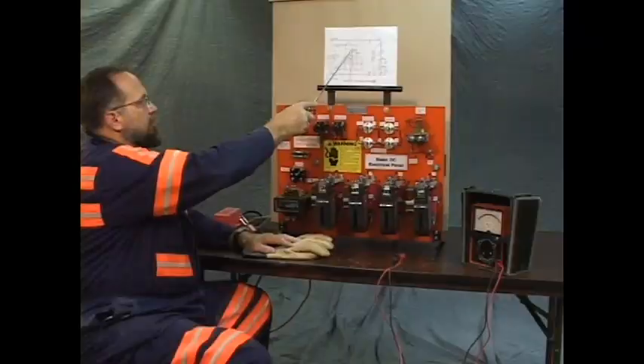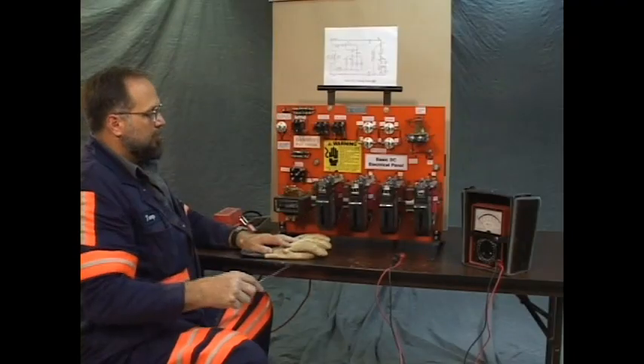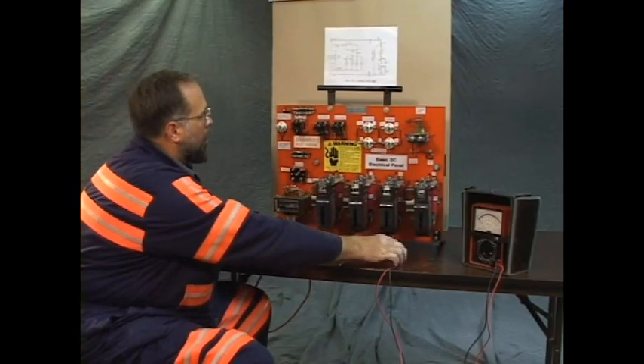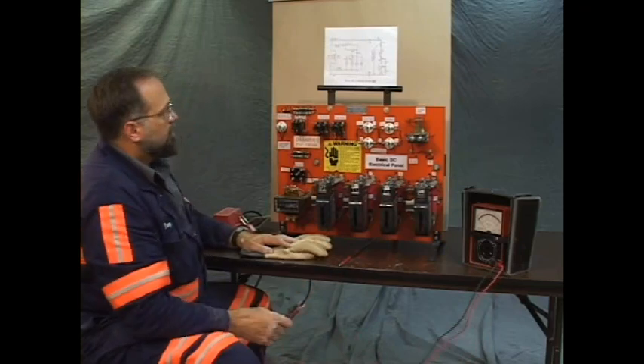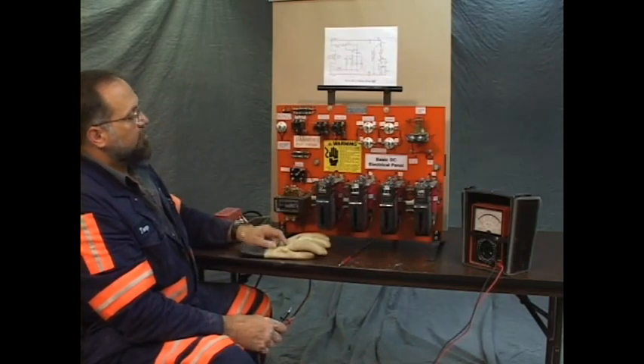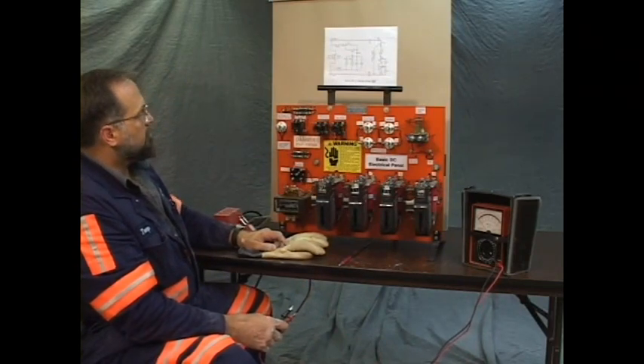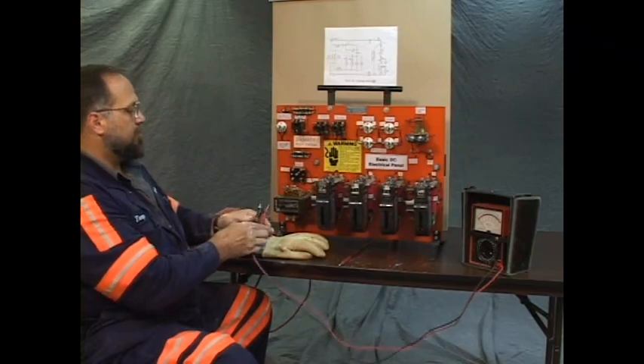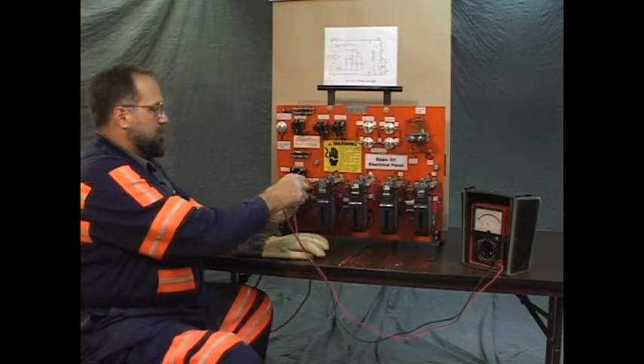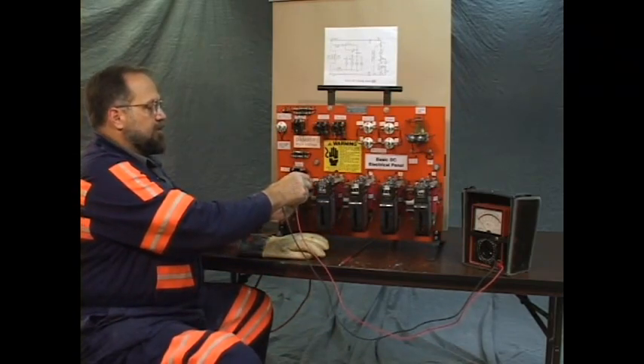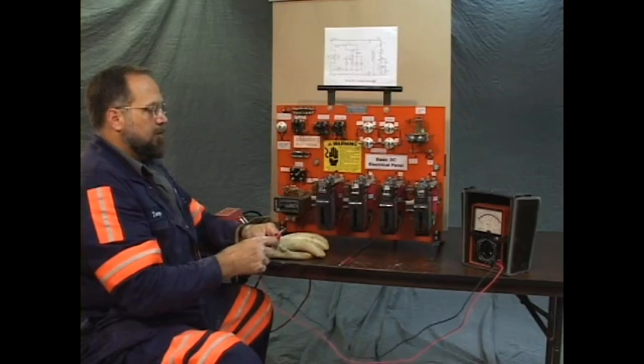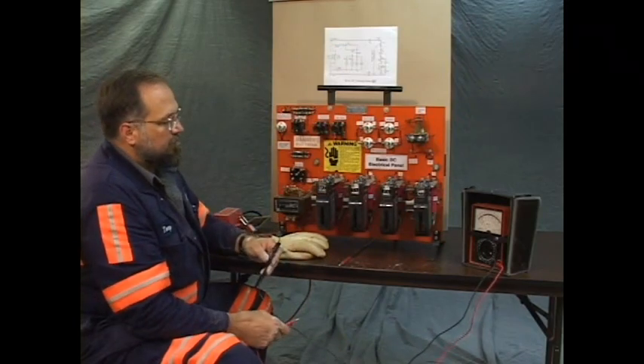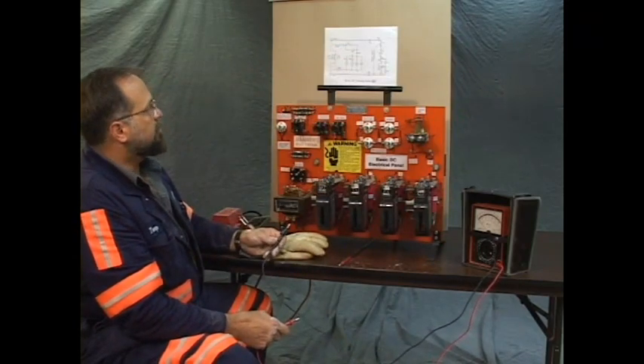Now, with the mercury tube and power off, all we can check on it is its normal status, whether it's normally open or normally closed. The print says it should be open, and indeed it reads open. So at this point in our testing, that's as far as we can go with testing of the tube.